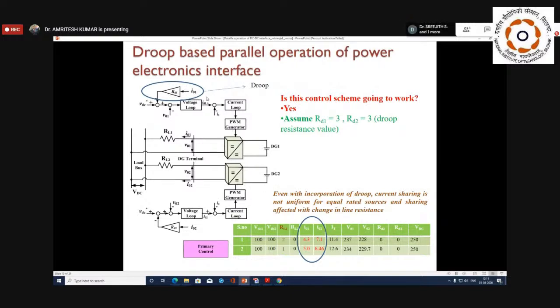Because if we are not applying this droop, there won't be any sharing. There will be non-uniformity in the sharing, and one converter might come under high stress if we are not incorporating those conditions. Okay, so first thing, is this control scheme going to work? Like previous time, we have seen that with the incorporation of line resistance, the normal voltage and current loop is not going to work. Your PI controller is always going to be in saturation mode. Your system will be out of control. So by using this droop control, without communication, we are able to control our converter in such a way that they share uniform power through each converter.